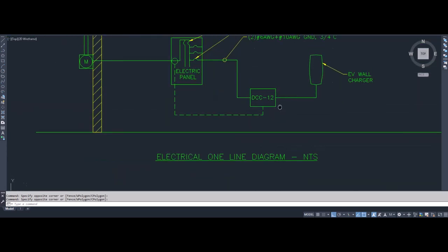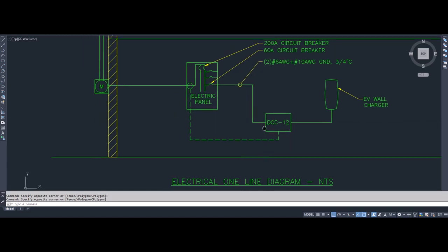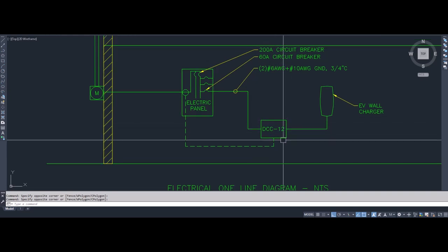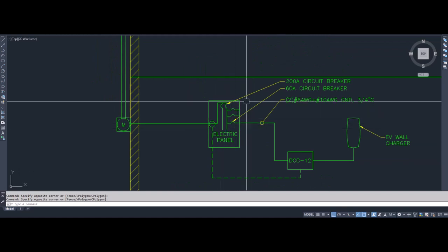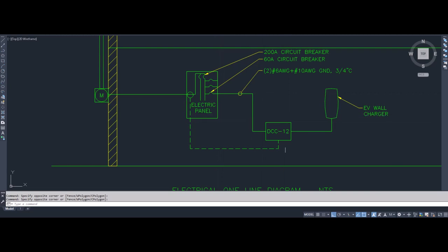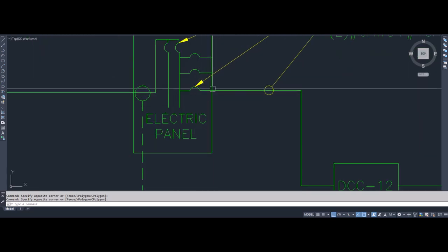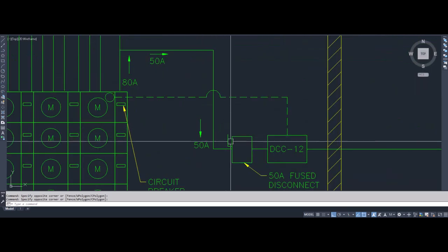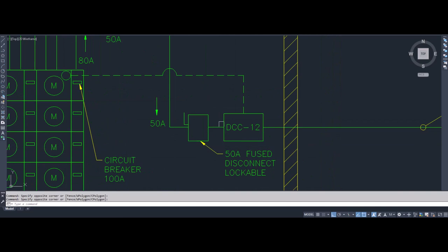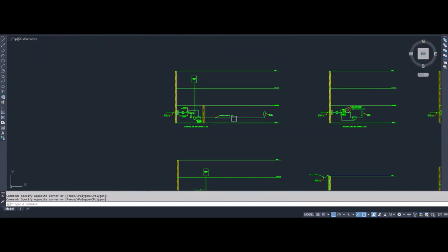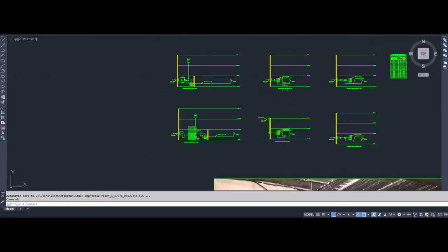And I prefer the installation of the DCC12 just because you can separately shut off the DCC12 if you had to do some sort of repair or replacement work without having to cut off power to anything else. You could just isolate the DCC12 since it is on its own separate disconnect. Same as with this example here, it's on a separate disconnect. Same with this, as well as here as well. So I would basically recommend installing the DCC12 in any one of these 4 configurations here, based on whichever one is most similar to the electrical service at your project location.